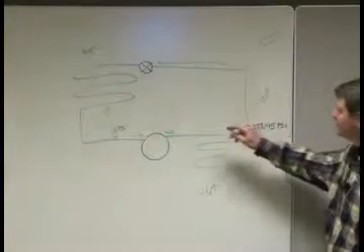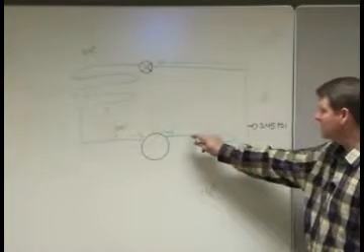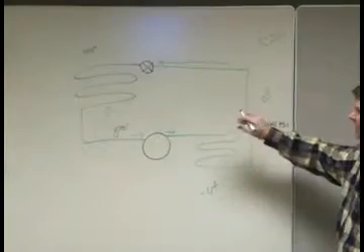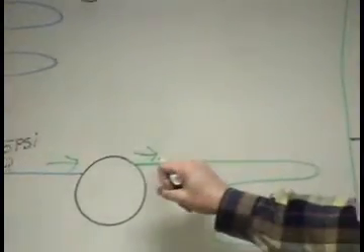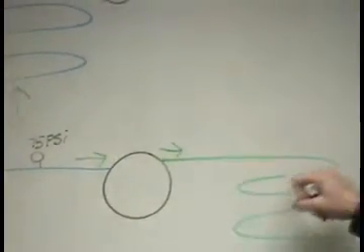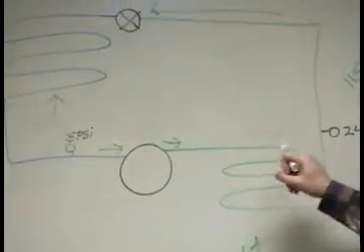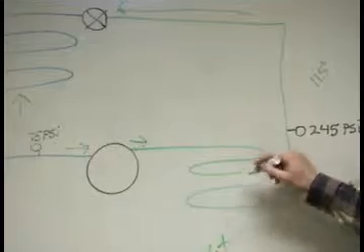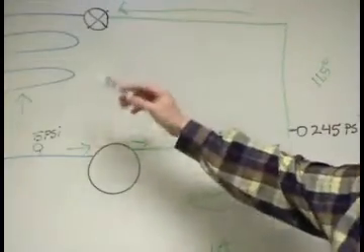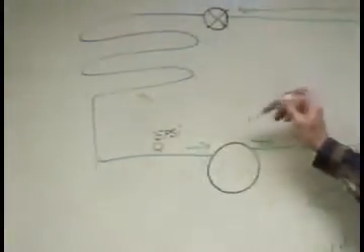What you do is it is piped in such a configuration that when you want it to be air conditioning, like you are right here, the discharge of the compressor goes to the condenser, the outside coil. Shouldn't call it the condenser anymore. It goes to the outside coil, and the inside coil stays just like this.